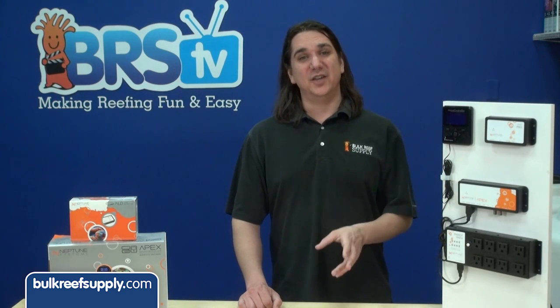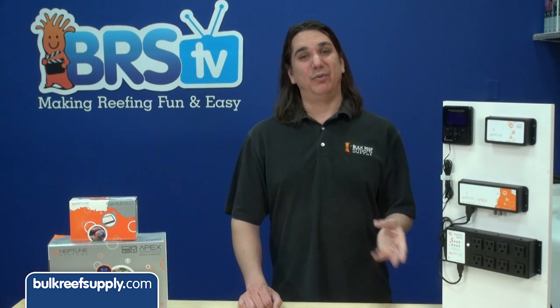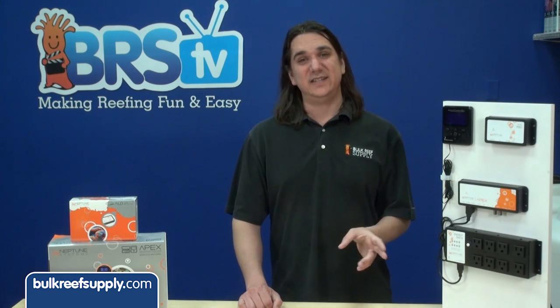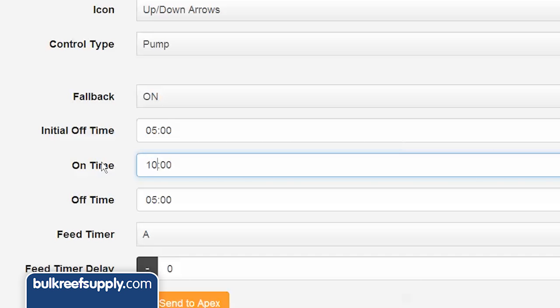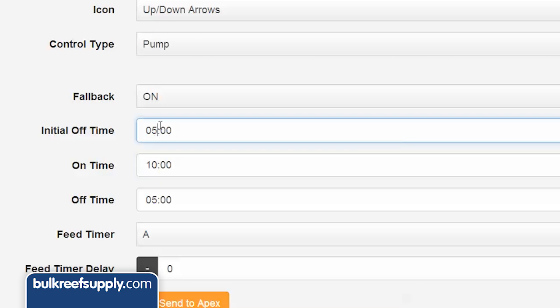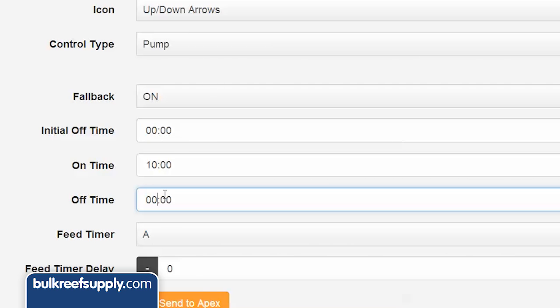The on time is how long you want the pump to be on during a cycle and is probably the easiest to understand. If I enter 10 minutes here, when the pump cycle is on it will stay on for 10 minutes. The only exception is if you enter zero for both the initial off and the off time — the pump will turn on for 10 minutes and stay on forever because there are no off commands.